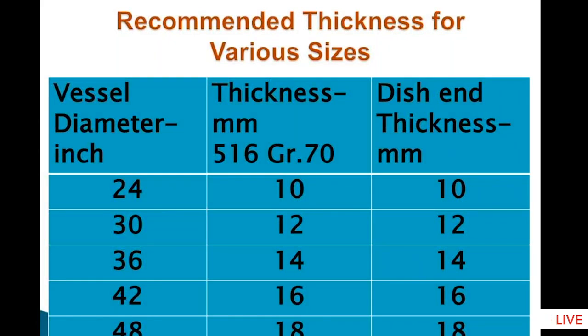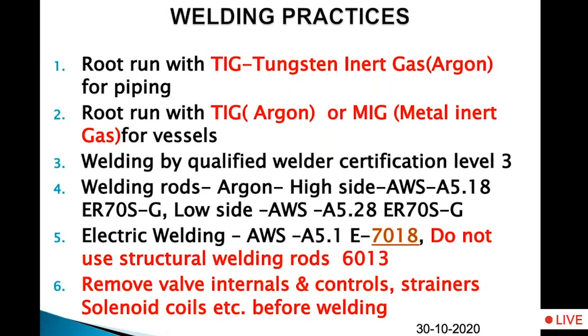Now, for the sake of easier understanding, for normal sizes of receivers, what we use is 24-inch, 30-inch, 36-inch, 42-inch, 48-inch, and I have given the ready reckoner thickness calculations: 10 millimeter for dish end, 10 millimeter for plate, 30 inches 12 millimeter, 36 inches 14 millimeters, 42 inches 16 millimeters, and 48 inches 18 millimeters. So this is a ready reckoner. You need not calculate. You can use this straight away, which I have calculated.